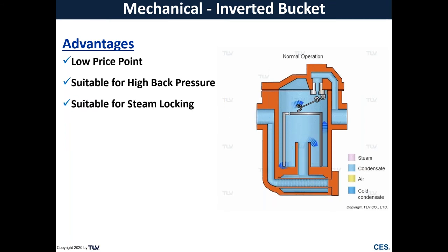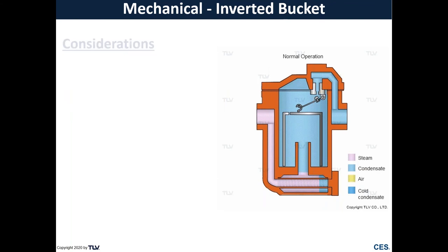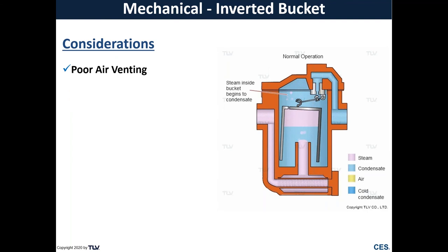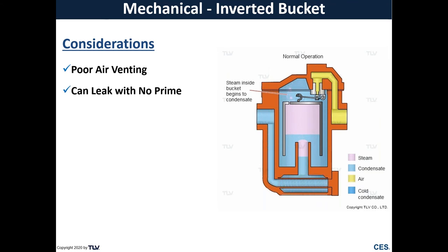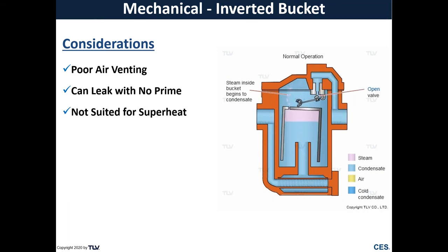And based on its operation, this is suitable to be installed on a steam locking application. Some considerations to think about with this trap is its air venting capability. So there's really just that, there's no added element for air venting. It's just that tiny weep hole, and that will bleed air as well as steam. Without having a water prime, this bucket has no way to float. And so if you lose that water prime for some reason, this trap will remain wide open.